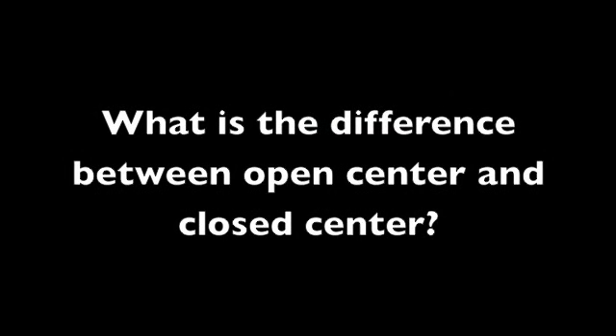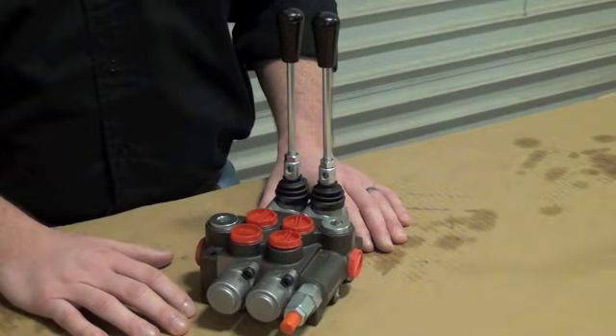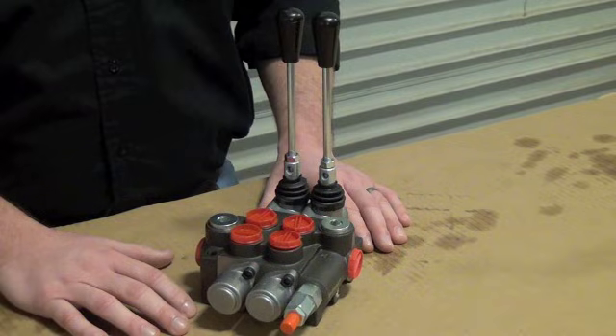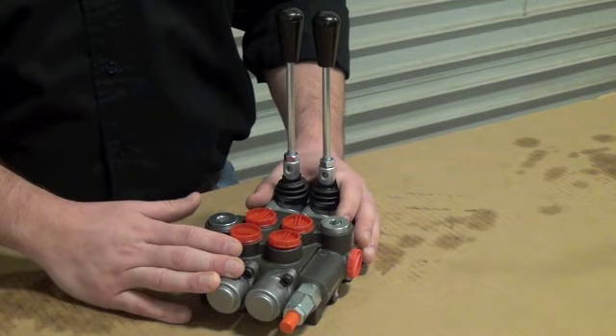What is the difference between open center and closed center? In an open center valve, the flow from the pump is allowed to pass through the valve and return to the tank when the valve is not in use. These types of valves are most commonly used with fixed displacement pumps like gear pumps.